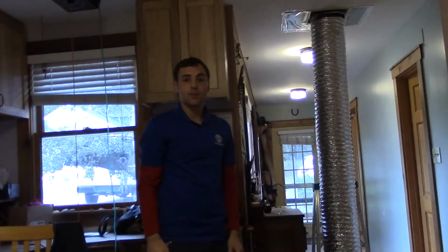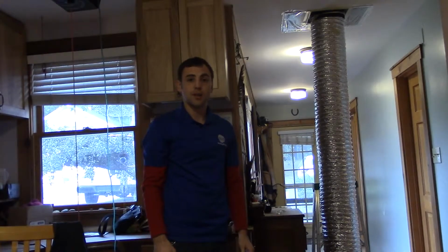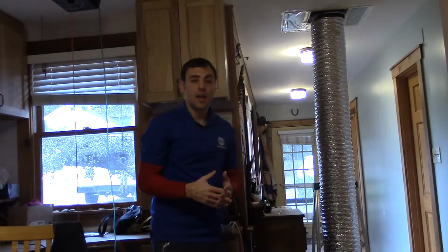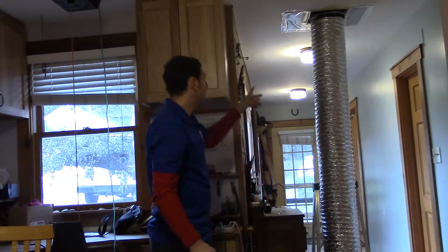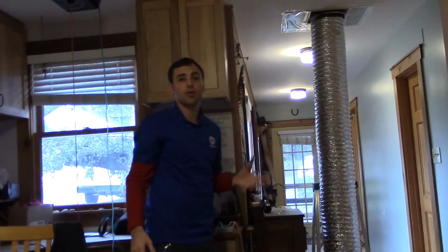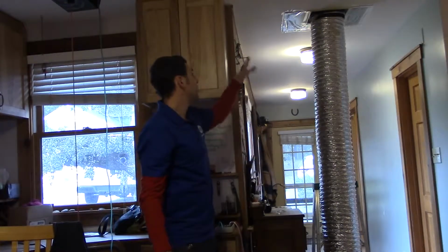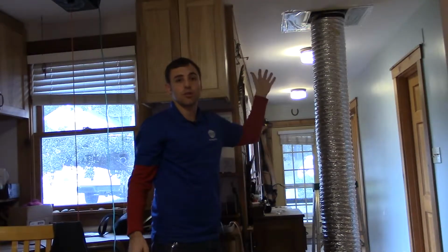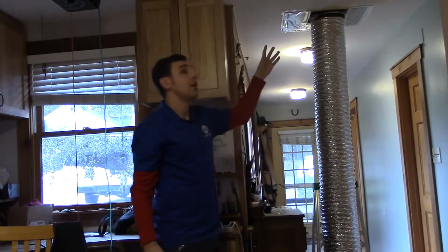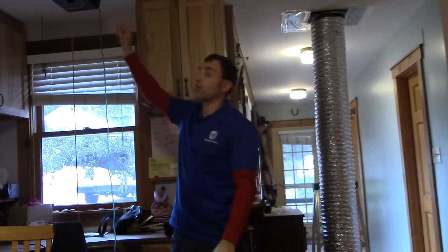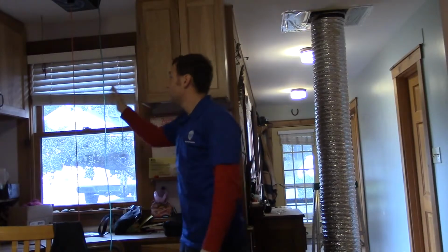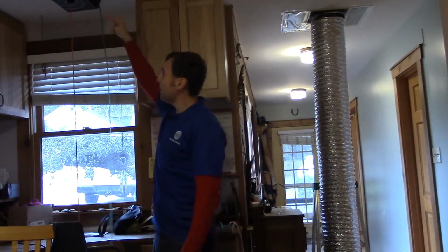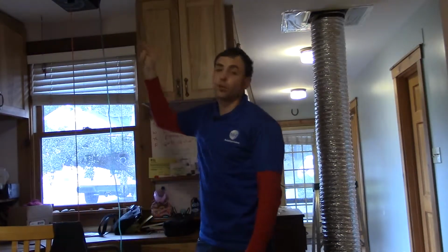Okay, so now I am set up to run a duct blaster test, and what this does is it measures the duct leakage. We have a fan here that's going to suck the air out and depressurize the ducts. We've hooked up to the main return, in this case the only return for this system, and we've taped off everything as well as all of the other supply registers. And this hose here is going in measuring the pressure inside the ductwork, so we know when we've reached our test pressure, which is 25 pascals.